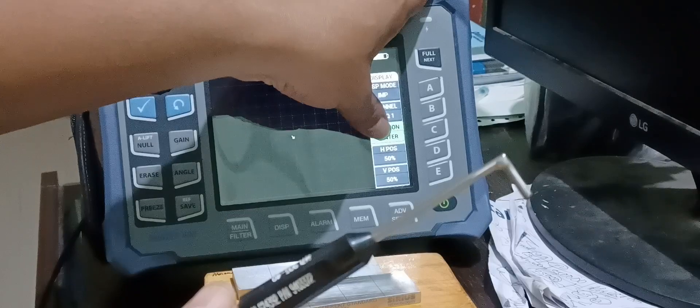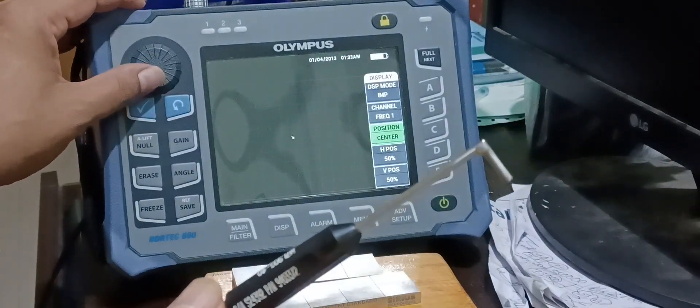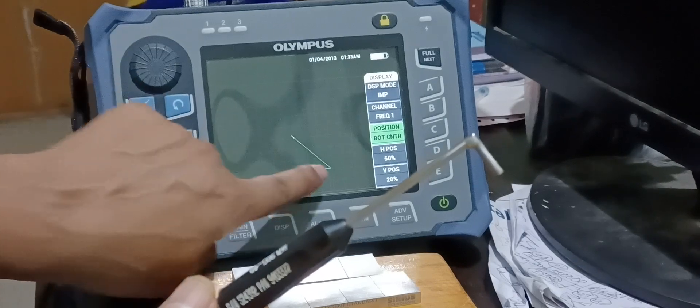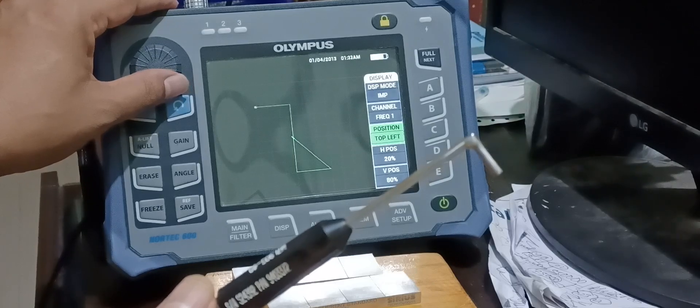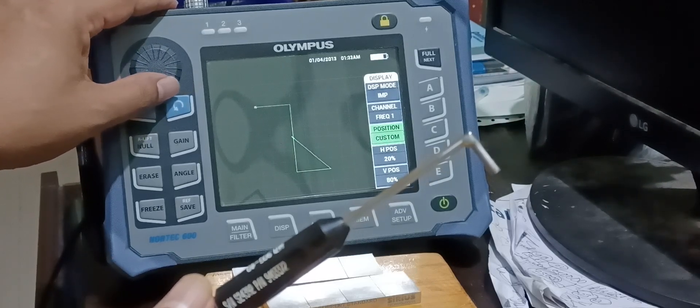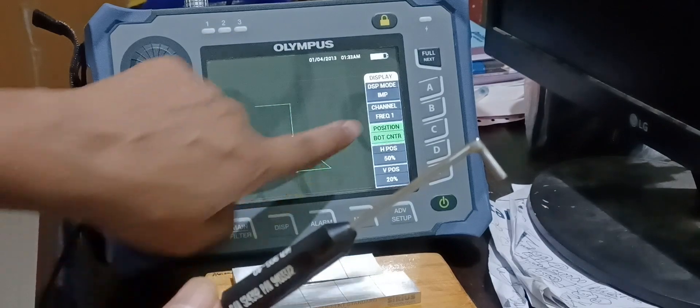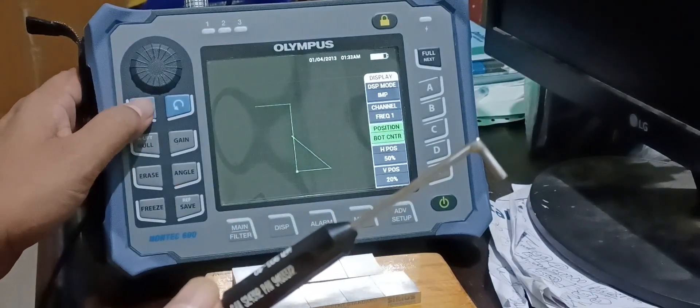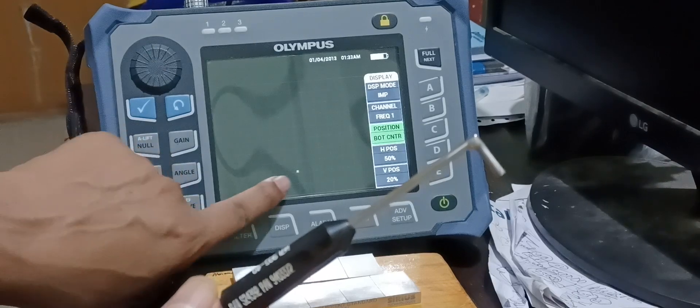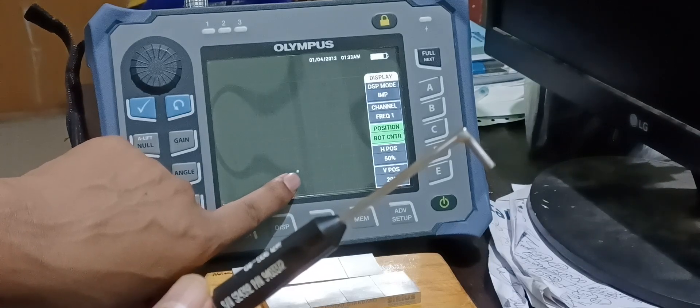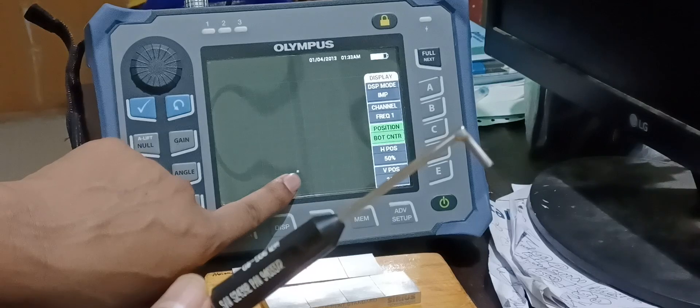Now, by the option C, when I press it, I have got this option highlighted in green color. The first position is position in center. I am changing it. It is bottom right. Now it is bottom center. You can see the movement of the null point. This is top center. This is top left. This is the custom. For the sake of our calibration, I am setting the null point to the bottom center. And again, I am pressing this right button. And null button. Now you can see, the air point or the null point, the air point comes down to the bottom center of the screen. When I press this, it is null. And the position is bottom center fixed.